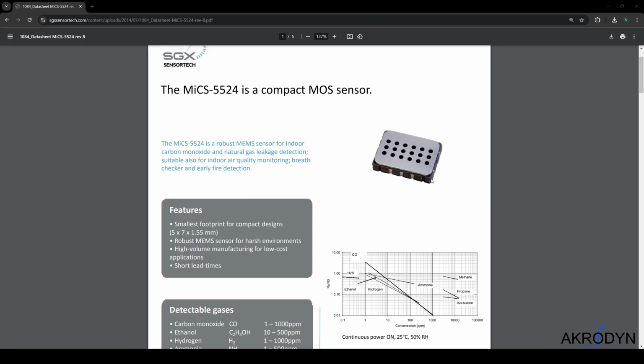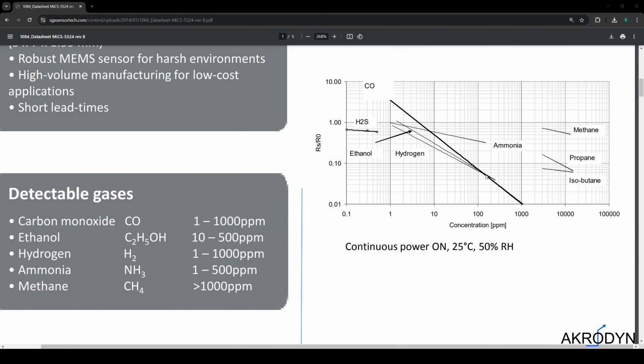Using the MICS5524 sensor module, here's an overview of the gases you can detect. We want ethanol, so on the bottom you see the concentration in parts per million. R0 is the calibrated internal resistance of the sensor module, obtained from air calibration, and RS is the new detected internal resistance after exposure to gas.